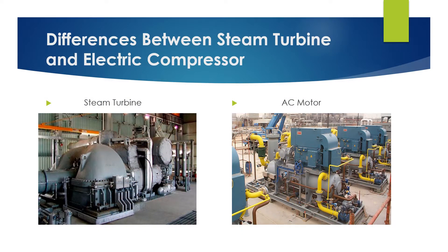According to industry representatives, the decision to select steam turbine versus AC motors with electronic-adjustable speed drives for rotary equipment is, for the most part, economically-based. For example, it is dependent upon the relative cost for steam production versus the purchase price for electricity. Other considerations include fuel and electrical energy costs, steam availability, and steam pressure and quality.